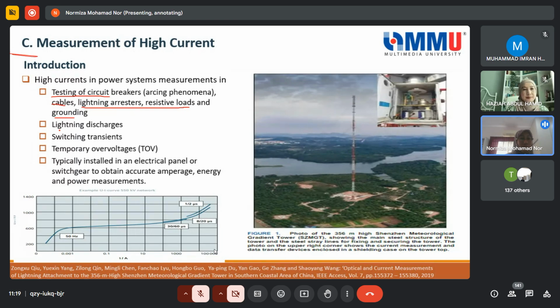In fact, if you go to many high voltage labs in Malaysia itself, you will find that most equipment is for generating and measuring high voltage, not high current. But anyway, it is still very much needed for testing of circuit breakers and resistive loads, where your load is the resistance, not the capacitance. I mean, it can be capacitance, but there are certain tests that require high current.